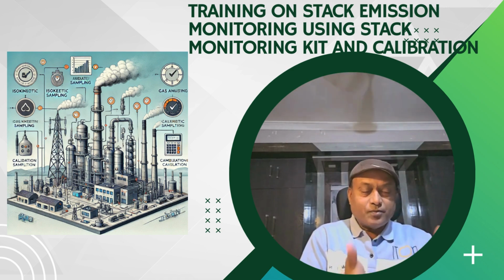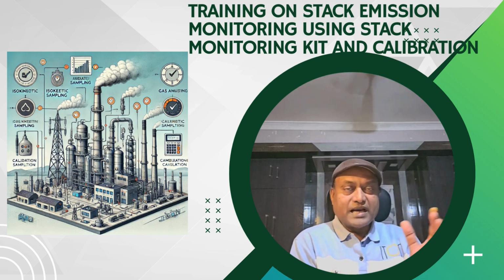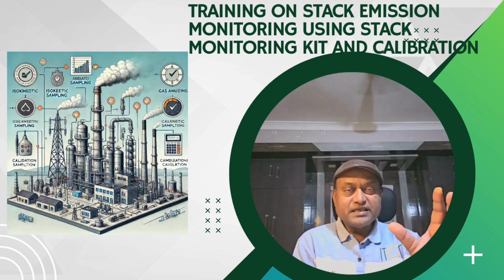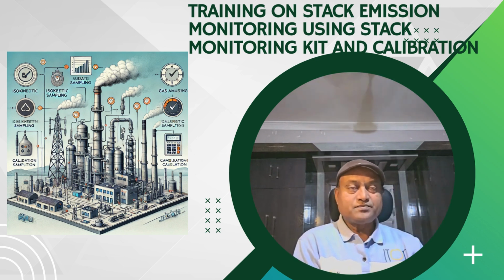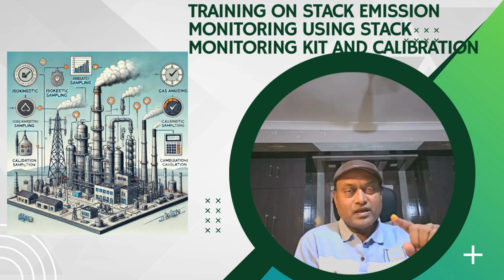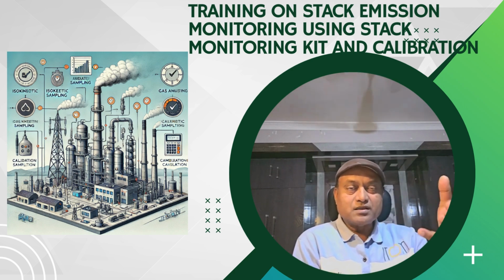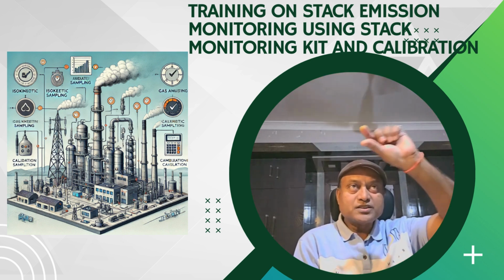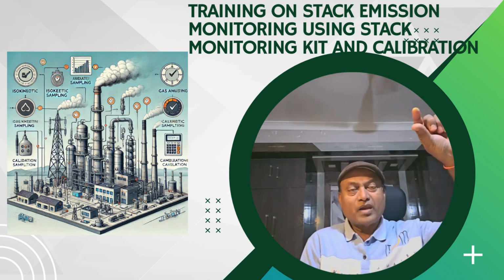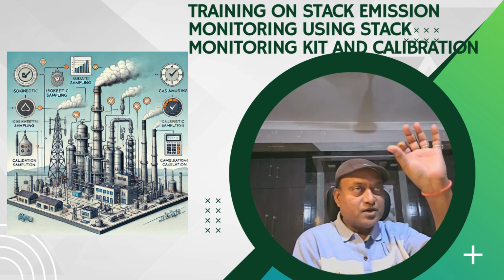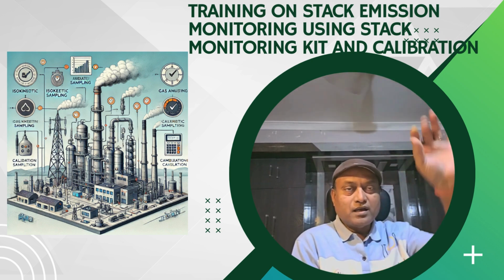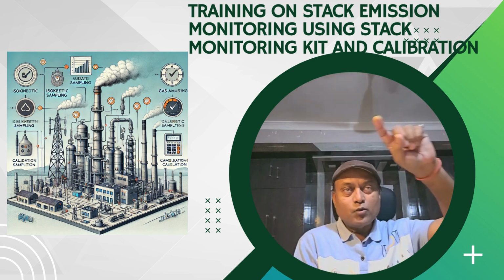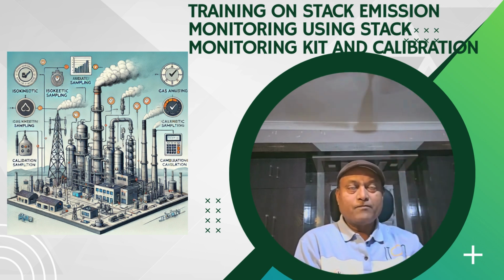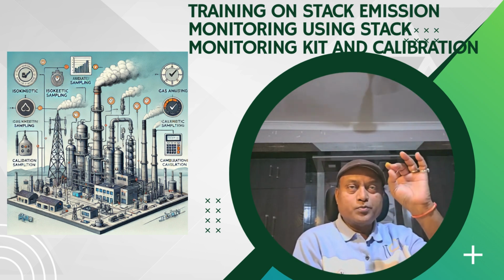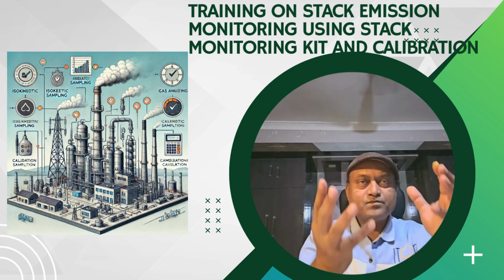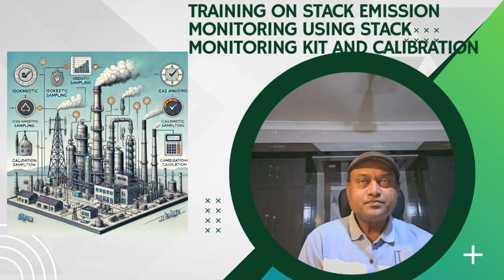At the base we measure the internal diameter of the stack, and then 8 times the internal diameter we have to construct the platform, and from this platform, up to the reachable point, we make a 4-inch diameter hole, and in this hole the probe is inserted and sampling is done.